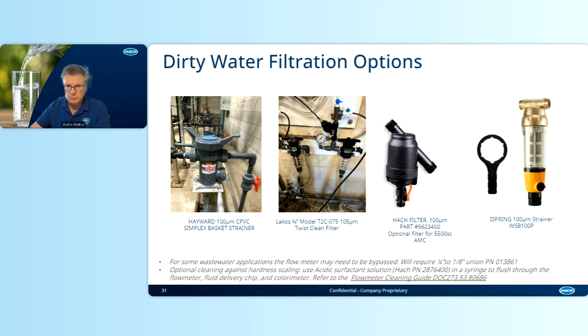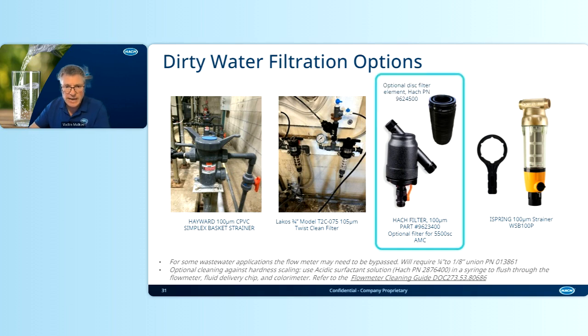And this filter is very suitable for dirty water applications with the CL17SC, especially if you apply the disc filter element, which is also provided by Hach. That disc filter has much higher capacity to filter out all those impurities, and it's much easier to clean and easy to replace. If you have a spare filter, it takes literally less than 5 minutes. I tested it myself, to swap the filter and let it work for another week.